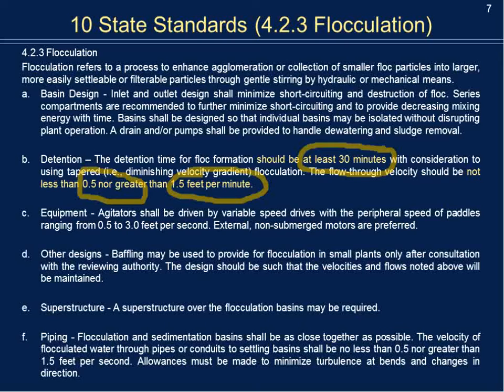The reason for the velocity range is you need enough speed — at least 0.5 feet per minute — so the floc doesn't settle out too soon (that should happen in the sedimentation tank), but not too high a velocity, because you want significant particle collision before moving to sedimentation. I highly recommend reading section 4.2.3 to ensure you meet all the criteria.